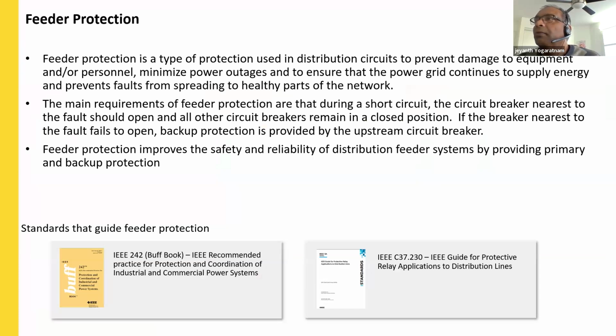Feeder protection is a type of protection used in a distribution circuit to prevent damage to equipment or personnel and to minimize power outages. It ensures that the power grid continues to supply the energy and prevents faults from spreading throughout the healthy circuit. The main requirement of feeder protection is that during a short circuit, the circuit breaker closest to the fault should open and clear the fault. And any breakers involved with the circuit which are not in the fault zone should remain closed and continue to provide the supply. This is called selectivity. If the breaker nearest to the fault fails to open, the backup protection is provided by the upstream circuit breaker.